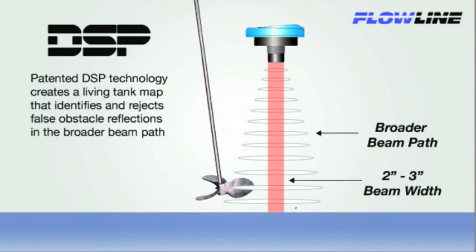DSP is able to filter out false obstacle reflections and track the true level of liquid. This gives Flowline ultrasonic sensors a 2 to 3 inch minimum beam width across the measurement range and increases the installation flexibility of the sensor.